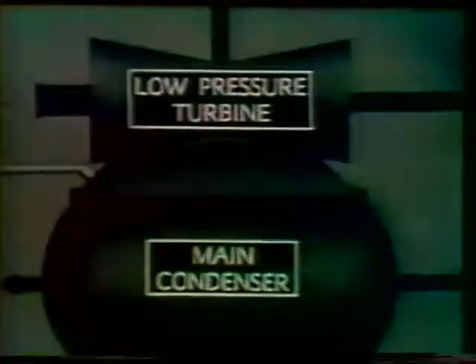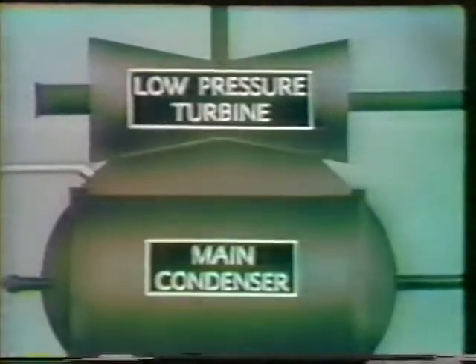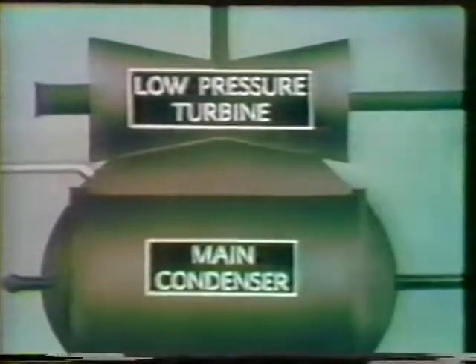If we could lower sea level, we could put in another dam at the mouth of the river, and thus get more work out of the river. In the next phase of the steam cycle, we can do this very thing with steam by reducing its pressure below the pressure of the atmosphere. This final reduction in steam pressure is an important function of the condensation system. It is the condensation of the steam in the main condenser which causes this reduction to below that of atmospheric pressure and makes available extra energy to turn the turbine rotors.